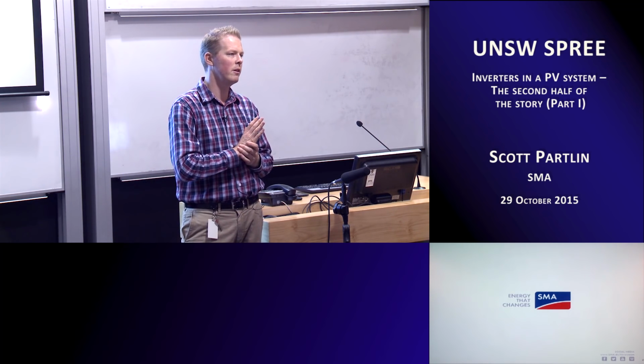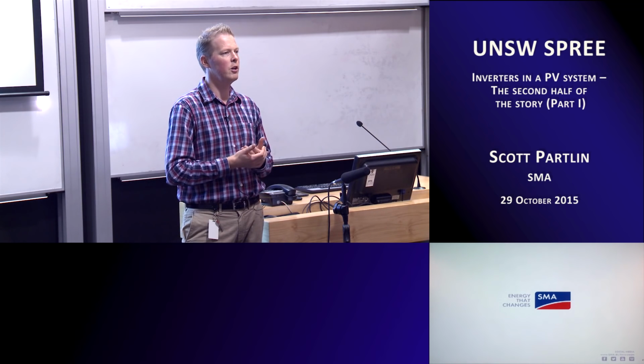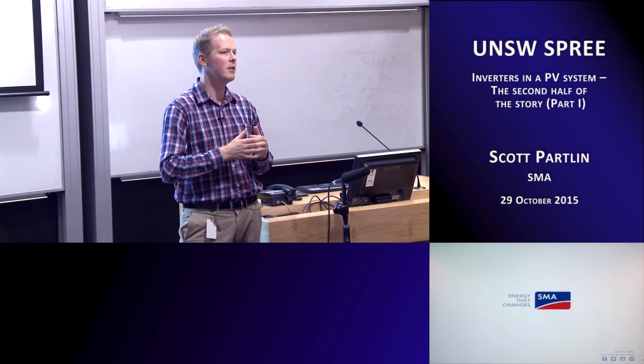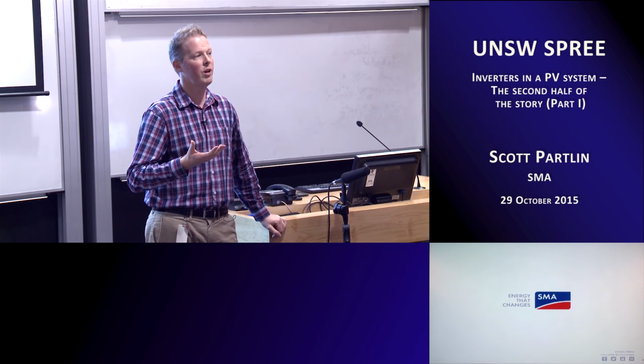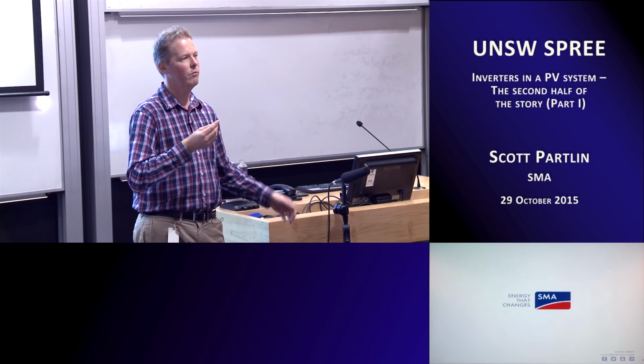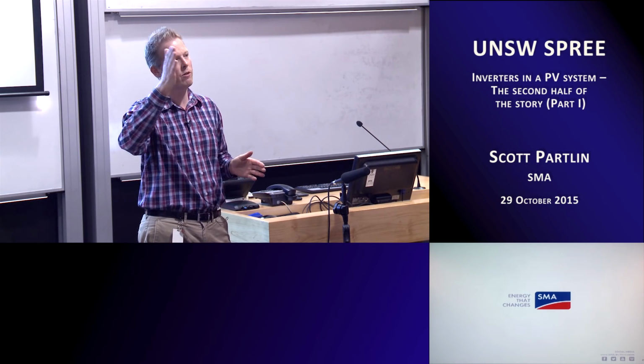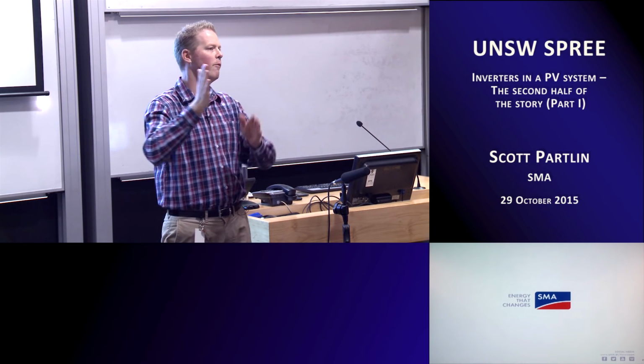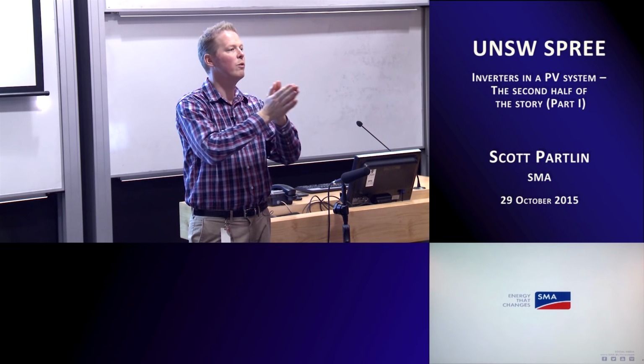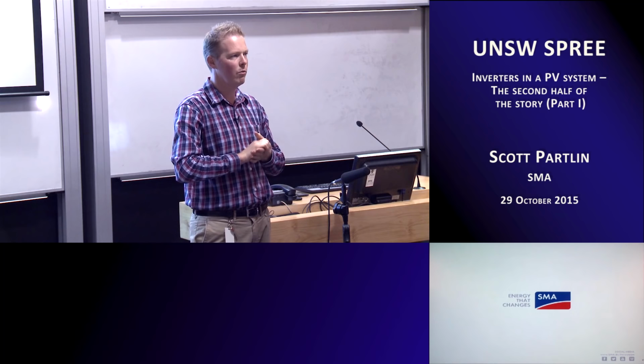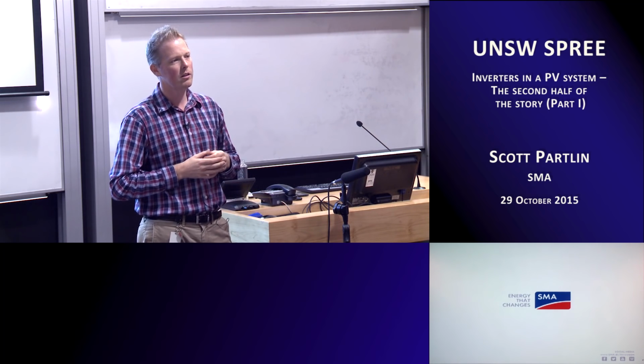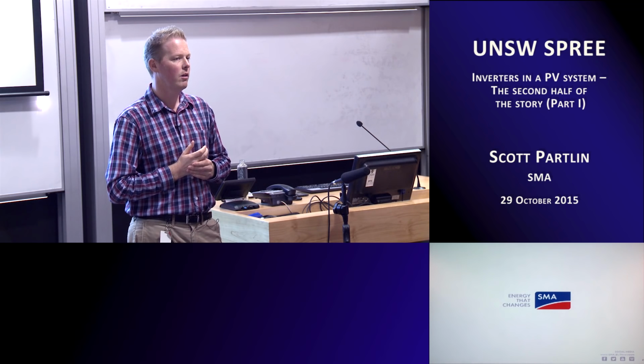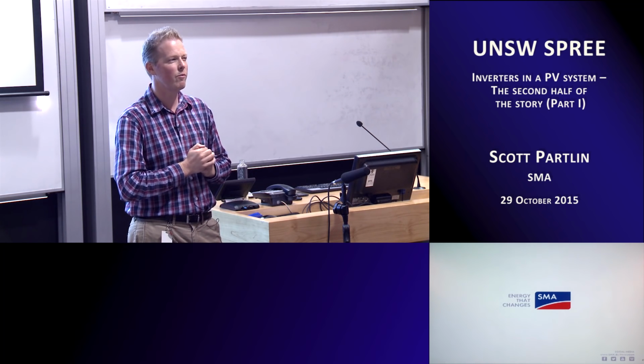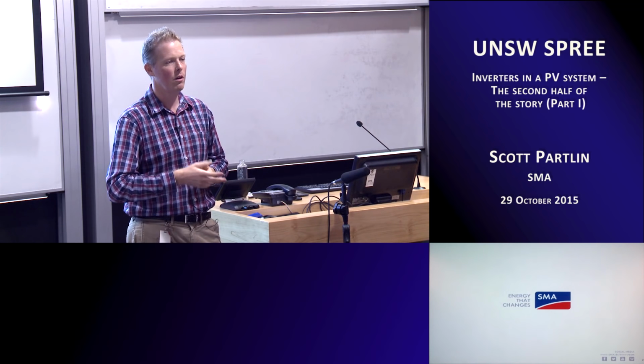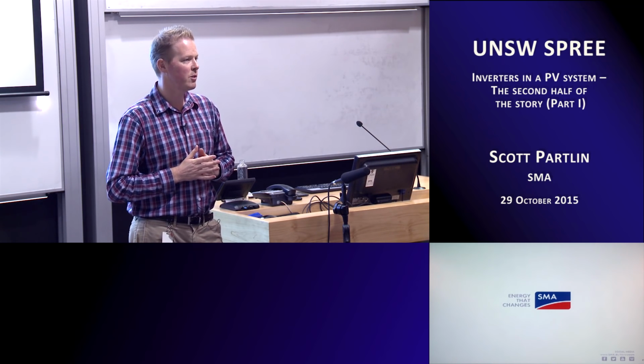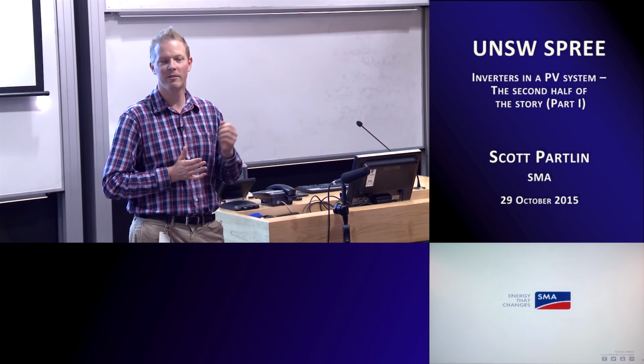It stays a lot more rock solid, and it's also one of the reasons that in utility scale solar plants and large commercial installations, they'll tend to oversize PV arrays so that from day one, the voltage window might be at the upper end of that voltage window, and over time, as the PV modules degrade, they're still within that voltage window. So the voltage window within the inverter doesn't degrade. Its AC output doesn't really degrade that much. If it's delivered as a 5 kilowatt inverter, it's still almost a 5 kilowatt inverter at the end of its life, or until some component loses its magic smoke, which doesn't happen that often.